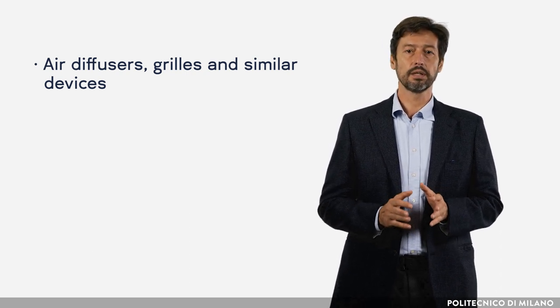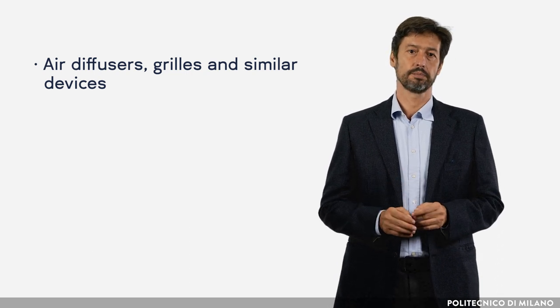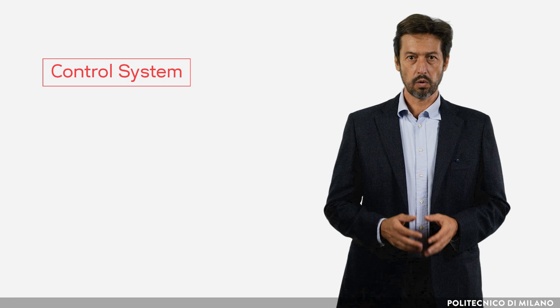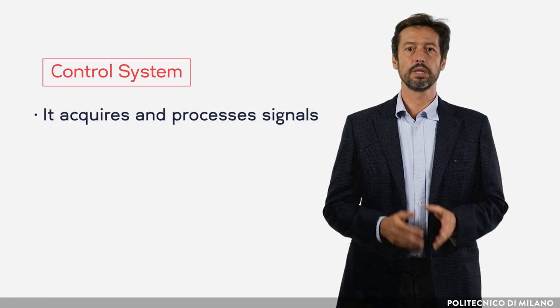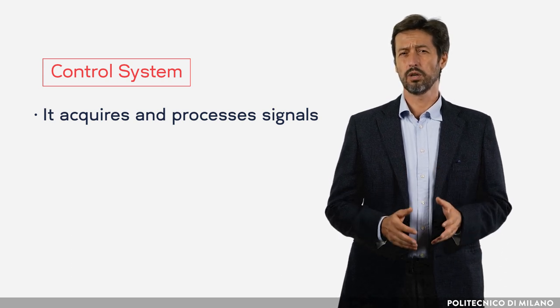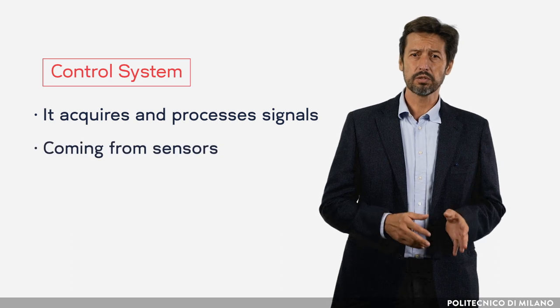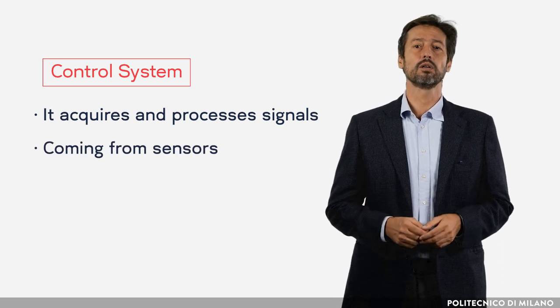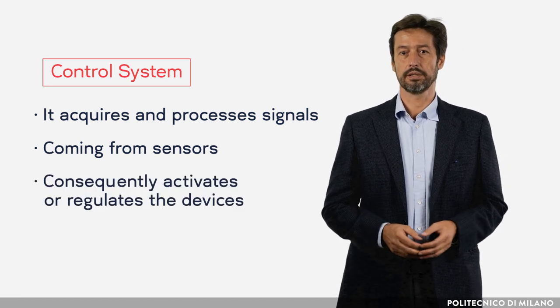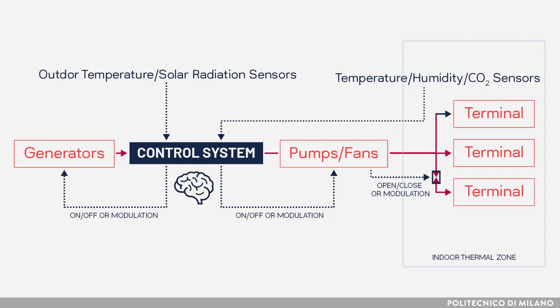Every system operates through a control system. It acquires and processes signals regarding temperature, humidity, or other parameters — for instance CO2 concentration — coming from sensors placed inside or outside the building, and consequently activates or regulates the devices. For instance: on-off or power modulation of the generator, on-off or power modulation of pumps and fans, opening, closing, or regulation of an air damper, and on-off or water flow modulation of a humidifier in the air handling unit.